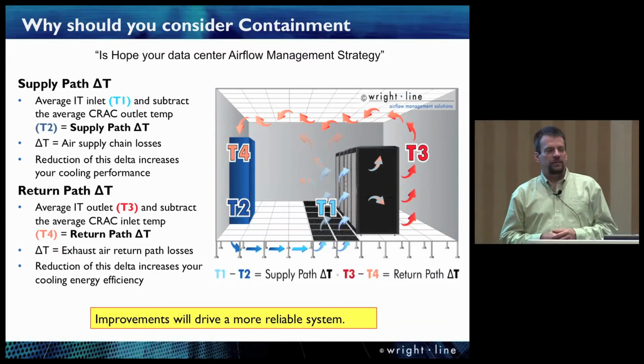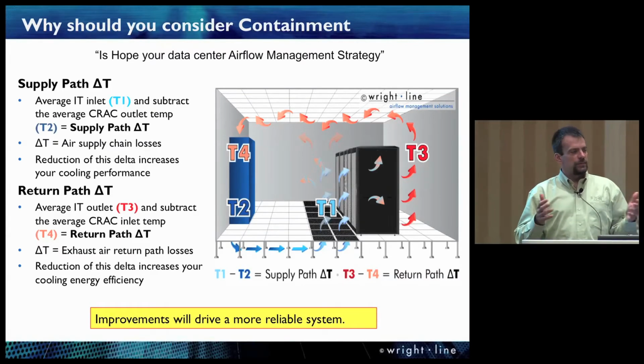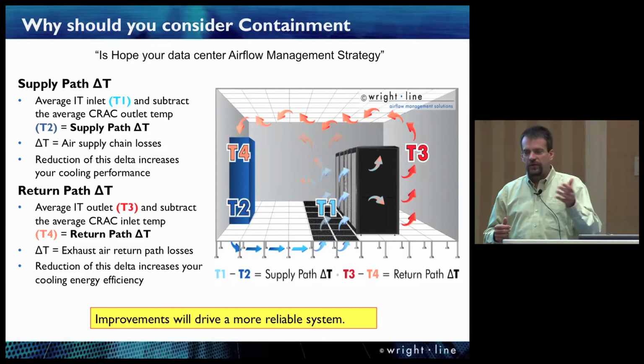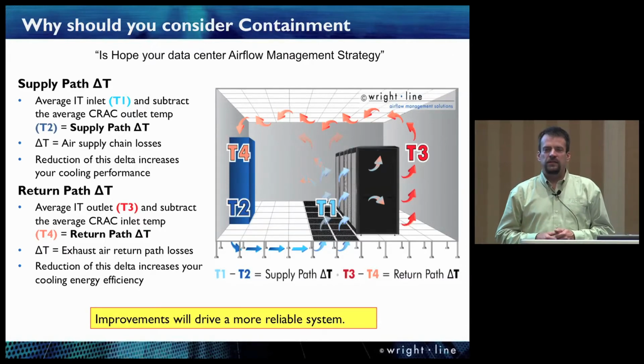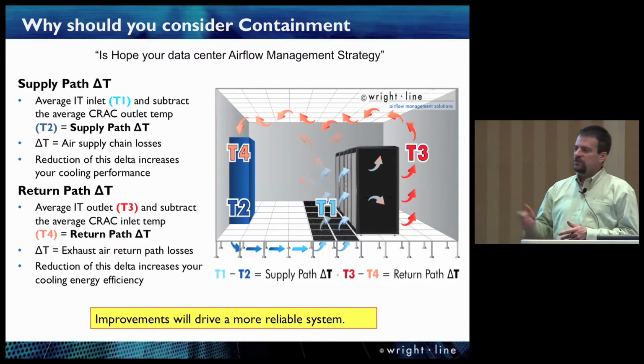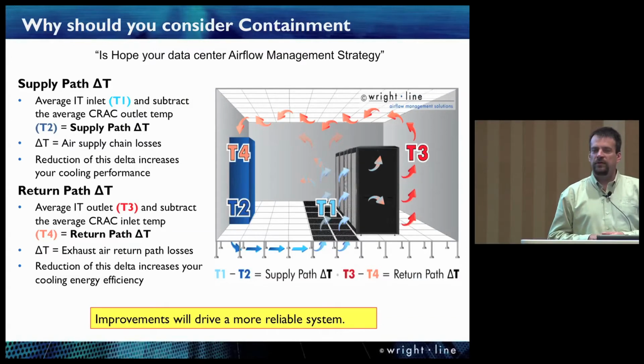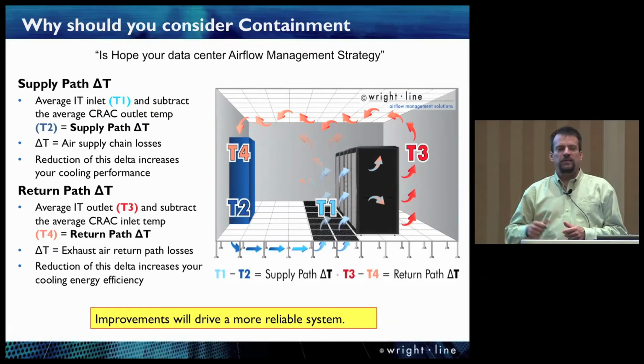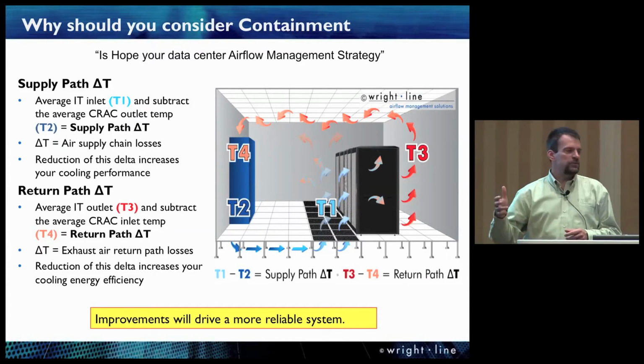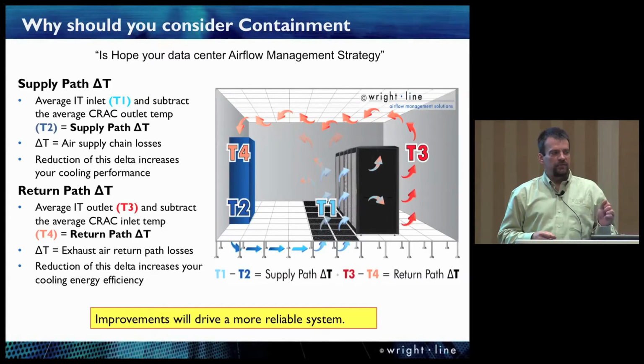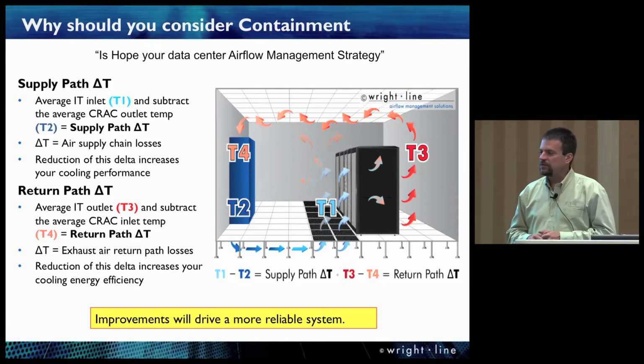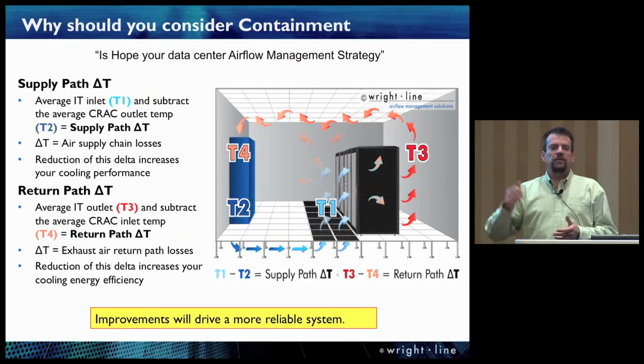Simply looking at the drawing gives you a real good idea of what the supply path delta T is. You've got air coming out of your HVAC equipment, represented here by just a perimeter type CRAC unit, and air that's brought into your IT equipment. If I was going to take the average inlet of all the IT equipment and the average outlet of all the supply air, there'd be a delta T there in a legacy data center. The wider that delta T is, the more chaos cooling exists in your data center.